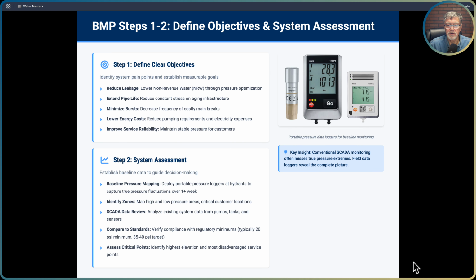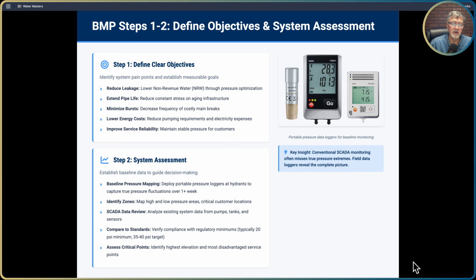All right, so let's look at these in a little bit more detail. Defining clear objectives. We need to know what we're going to be doing before we start. So we want to identify our system pain points and establish measurable goals. You can't measure progress without having the goals and being able to measure them. If you can't measure it, you can't improve it. So our goals: reduce leakage, lower non-revenue water through pressure optimization, extend pipe life, minimize the bursts, so decrease the frequency, lower energy costs as part of that, and improve service reliability. So we're not popping these leaks at night, and maintaining a stable pressure for customers.